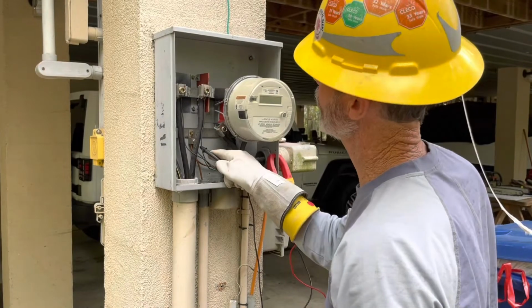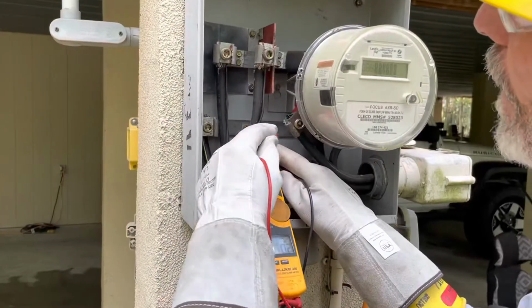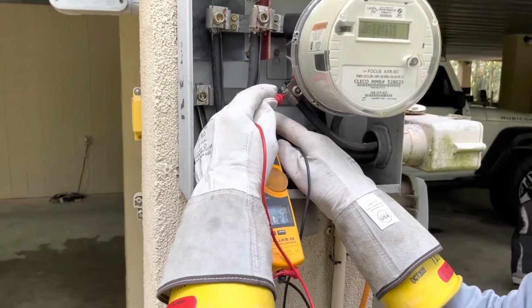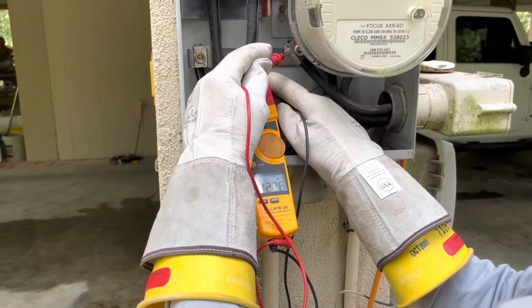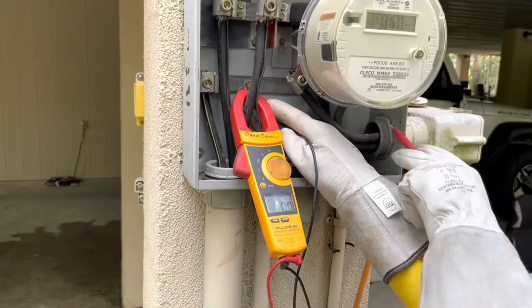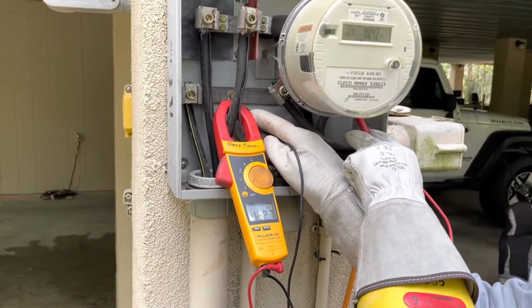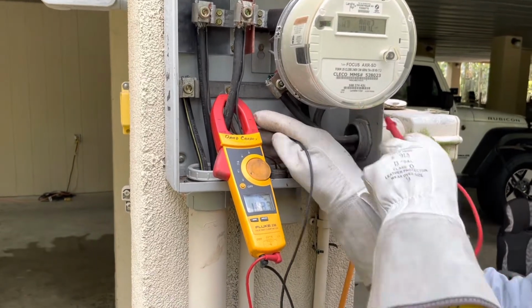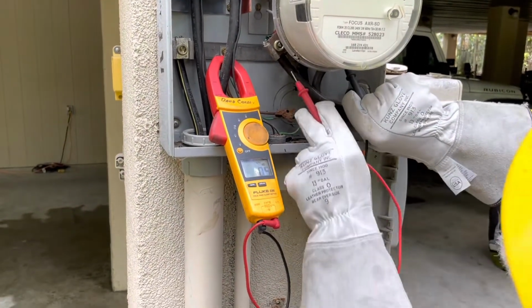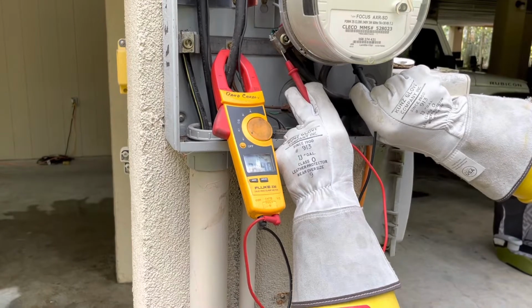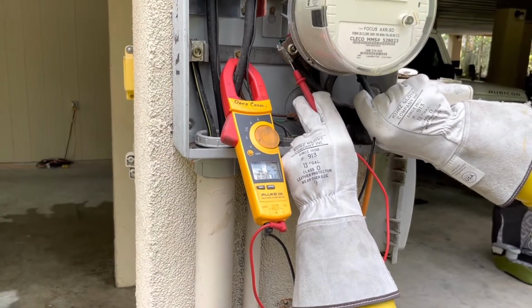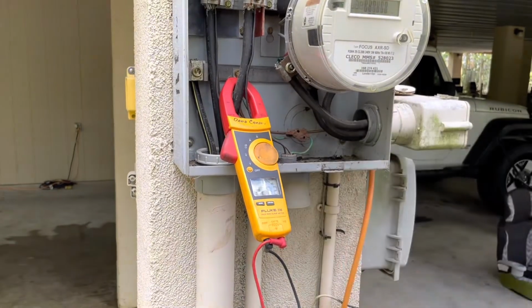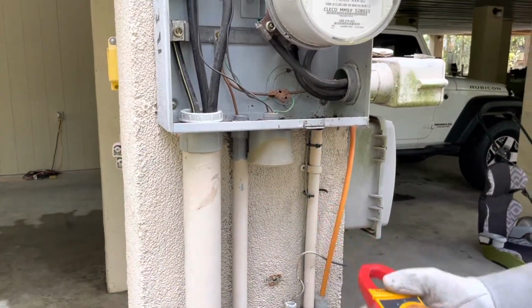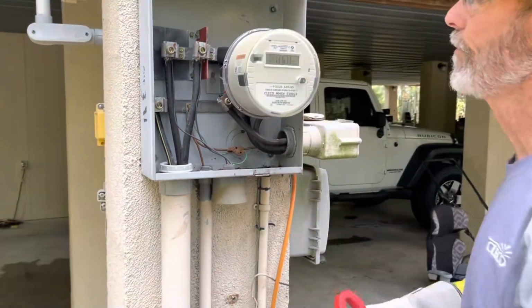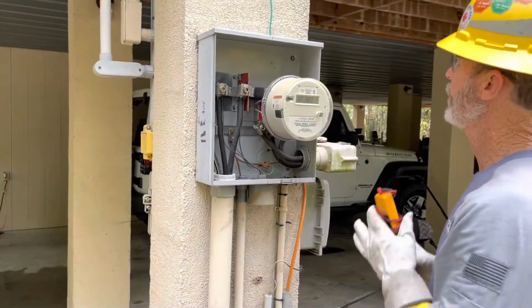So what I'm gonna do is I'm gonna go to ground. This is the load side of that breaker. So what I wanna see is 120 volts, which we see on the bottom left leg. And in the right leg, we got 122 volts. And then we're gonna go phase to phase, and we should have 240. Okay? So this is a good installation. I can go ahead and seal the meter pan up, and everything's good on this site.